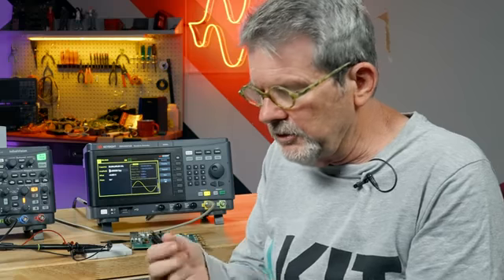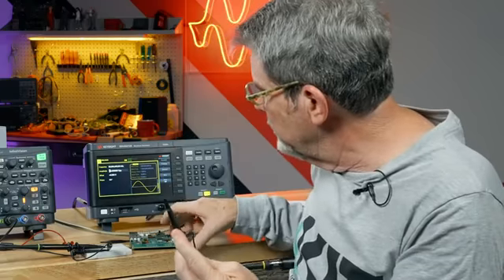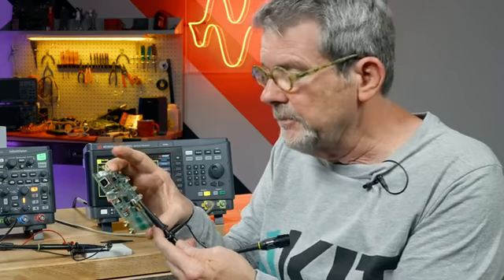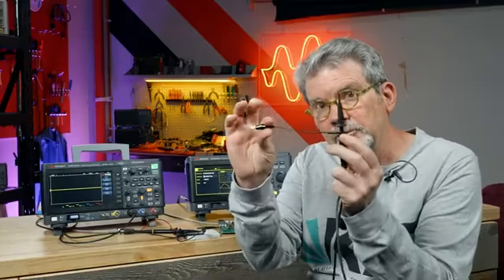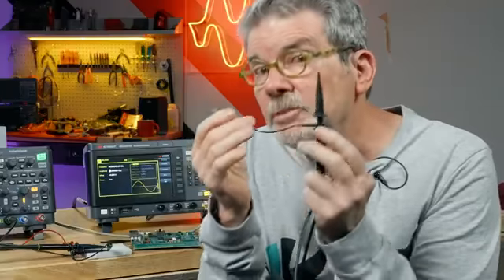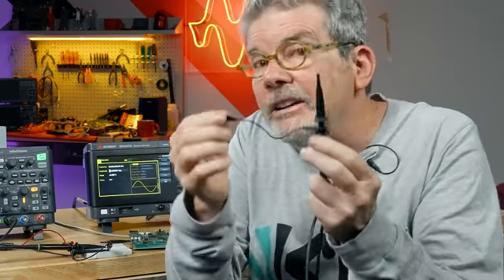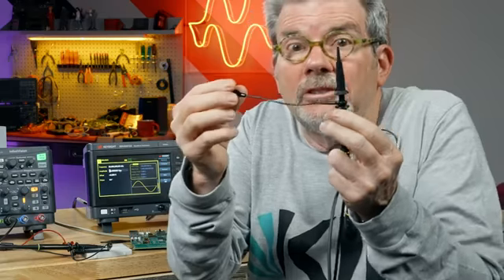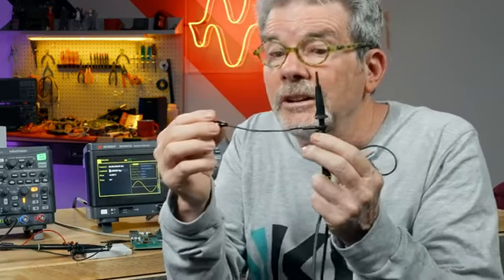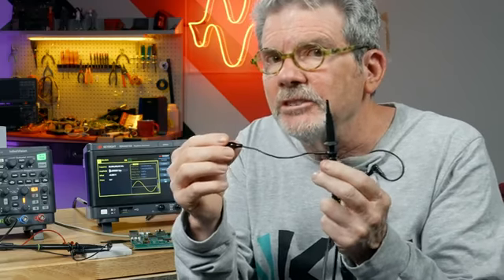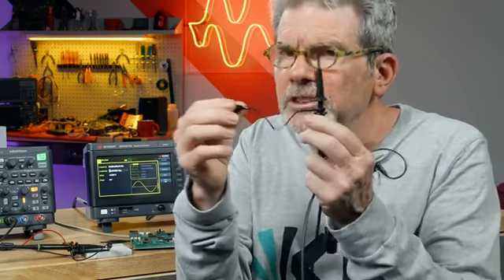You can also put on this retractable hook tip connector. And now I don't know if you can see it, but you can hook onto pins and test points and probe very easily. Now, this is the ground wire. It must be connected to ground. You can't connect it mid-circuit. The ideal model of this wire is just a 0 ohm wire, but it also has inductance in it. So if you're measuring very high frequencies, the inductance of this wire can make a big difference, and you need to use other adapters to make a shorter connection.